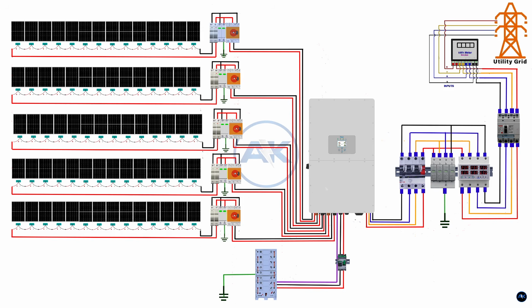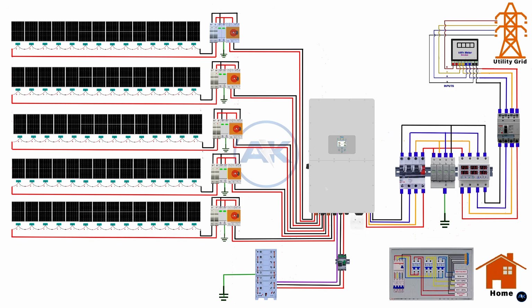Next, we connect the AC output side for the loads. The inverter AC output feeds the building loads through a separate load MCB. This breaker protects the load side and allows isolation of the building from the inverter. Use a 3-phase load MCB rated according to the load current, typically the same or slightly lower than the grid MCB rating. Connect the inverter AC output terminals to the input of the load MCB. From the output of the load MCB, connect L1, L2, L3, neutral, and ground to the main distribution board of the home or facility. All building loads will now receive power from the inverter when solar or battery energy is available, and from the grid when required.